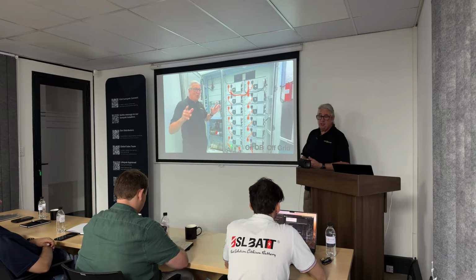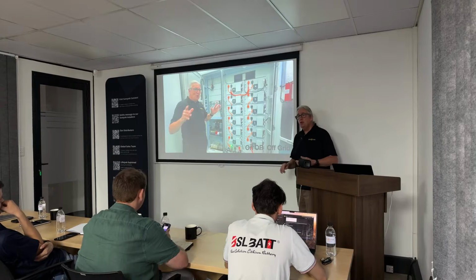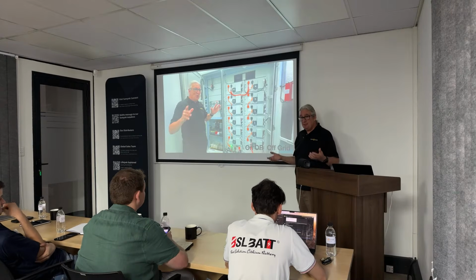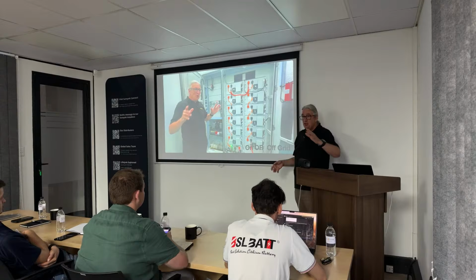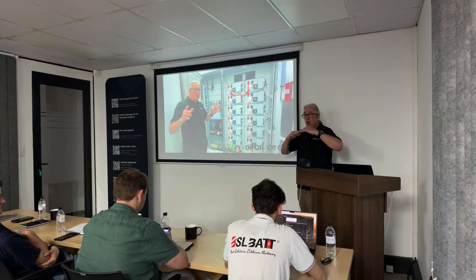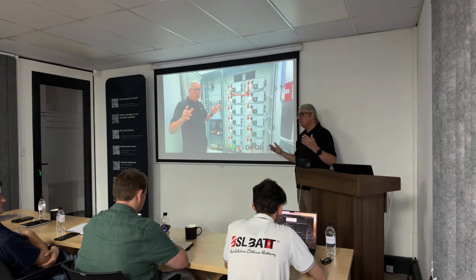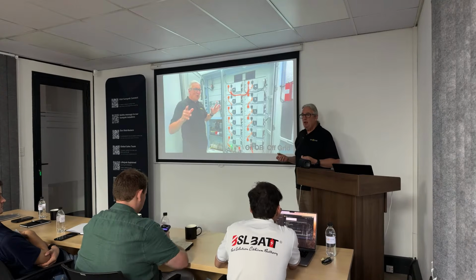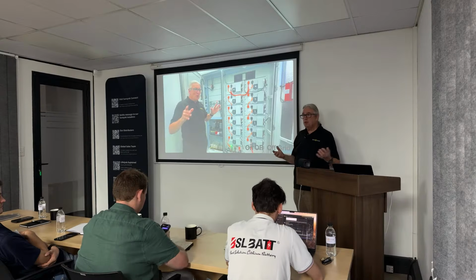One of the nice features we've got on power hubs is you can run a generator at the same time. So you might be having grid and a generator, and the frequencies don't need to lock. The generator can be charging a battery, and you might use a 50 kVA generator but have a 100 kVA load at some point - then the generator can directly charge it, directly DC couple the batteries. It can charge the batteries directly.